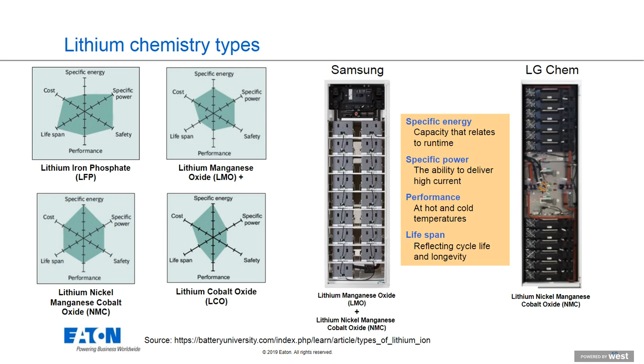Many of us in data center energy are used to replacing traditional UPS batteries every 5 years, maybe 6 if lucky. Lithium comes on board and says it can operate in this environment for a 15-year service life, about the length of the UPS system's own operating life. Keep in mind the warranties from these battery vendors are in the 10-year range, so that's probably the number to use for budgeting. But we're talking about doubling the service life of the battery, and even if the upfront cost is a bit more, the total cost of ownership over the UPS lifetime can drop pretty dramatically. It's a very attractive situation.